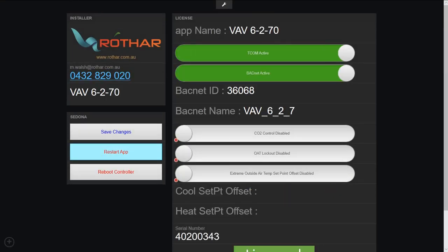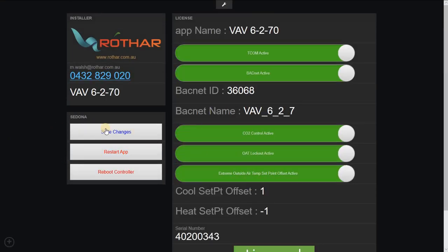Why do stuff twice, right? We're supposed to do the smart thing. Don't forget to save your changes. Just like in CPT, if you don't save and the controller reboots before it has a chance to autosave, your changes will be lost. Set your BACnet ID, your BACnet name, whether you want to use the carbon dioxide control or not. This program comes with CO2 control.